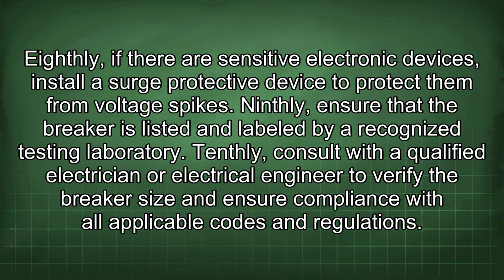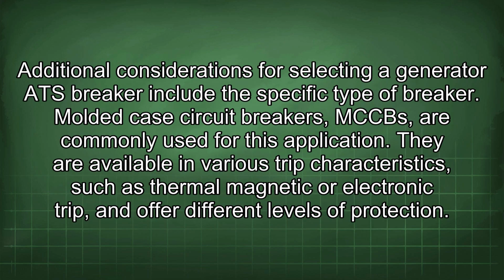Tenthly, consult with a qualified electrician or electrical engineer to verify the breaker size and ensure compliance with all applicable codes and regulations. Additional considerations for selecting a generator ATS breaker include the specific type of breaker. Molded case circuit breakers, MCCBs, are commonly used for this application. They are available in various trip characteristics such as thermal-magnetic or electronic trip, and offer different levels of protection.